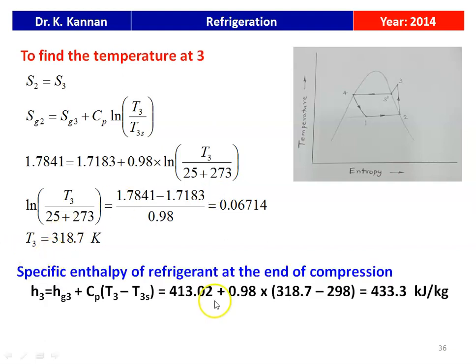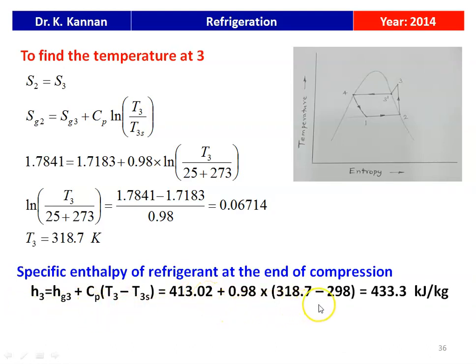Taking the antilogarithm and solving, T3 equals 318.7 Kelvin. The specific enthalpy at the end of the compression process is H3 equal to Hg3 plus Cp multiplied by (T3 minus T3s), which is 413.02 plus 0.98 multiplied by (318.7 minus 298), equal to 433.3 kilo joules per kilogram. The specific enthalpy of the refrigerant at the discharge of the compressor is 433.3 kJ/kg.